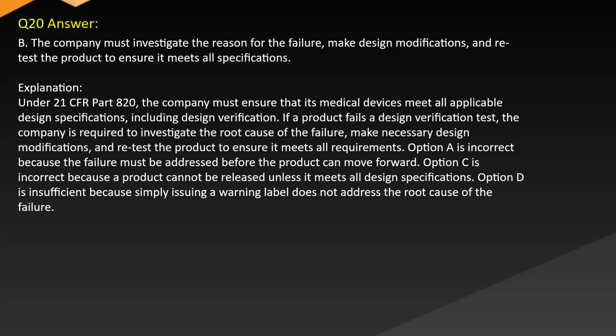Answer. B. The company must investigate the reason for the failure, make design modifications, and retest the product to ensure it meets all specifications. Explanation. Under 21 CFR Part 820, the company must ensure that its medical devices meet all applicable design specifications, including design verification.